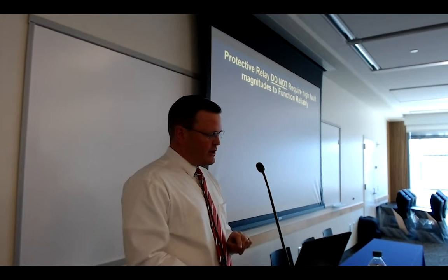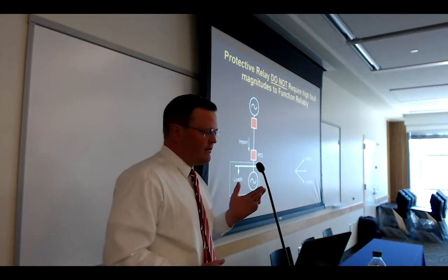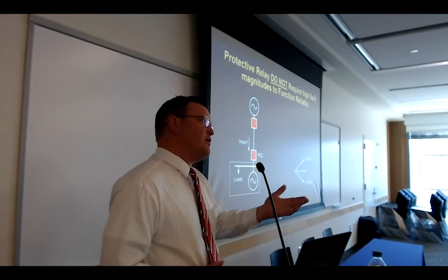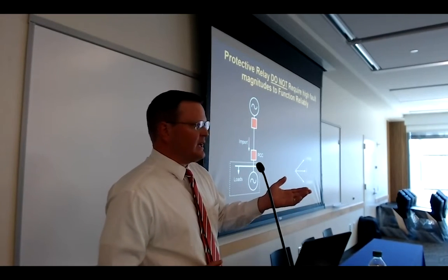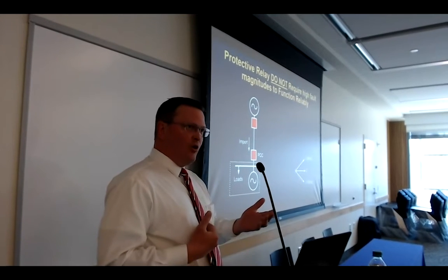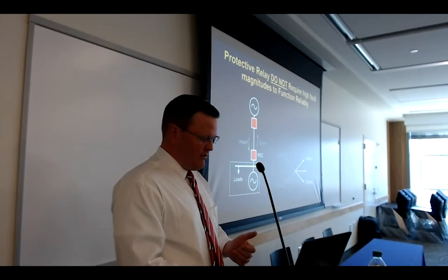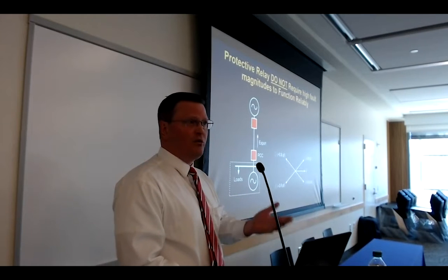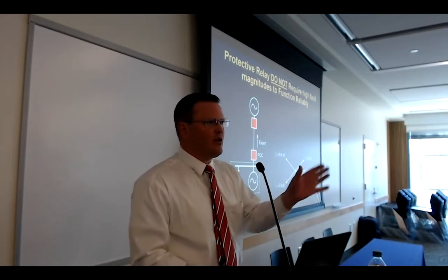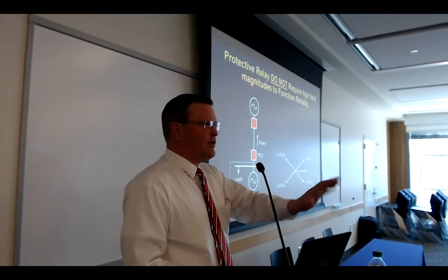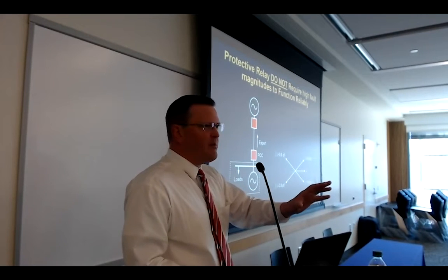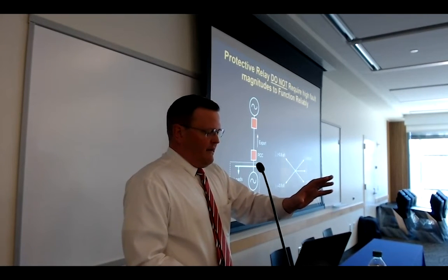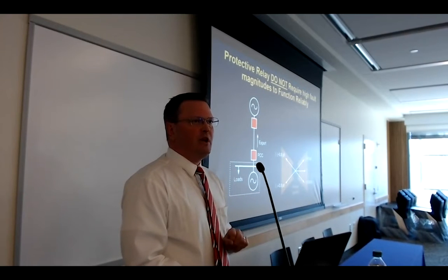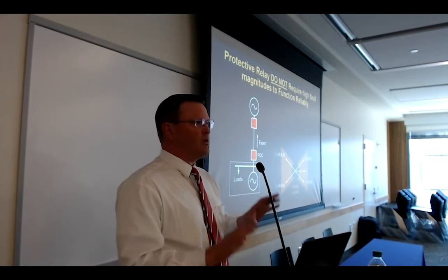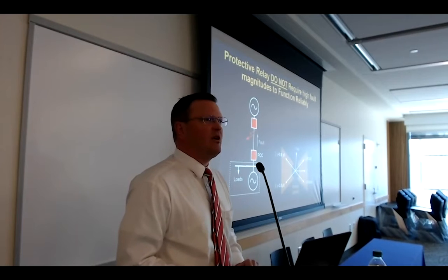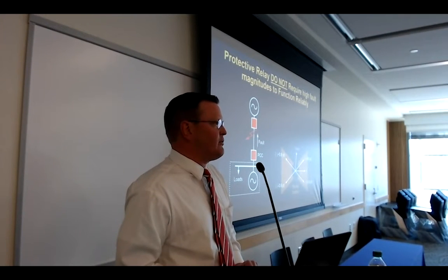Okay, so here's a scenario I'll explain. You have, again, that microgrid connected with some sort of generation connected to the macrogrid. During normal load import and export, you have phasor diagrams that look like this, currents related to voltage. I like this sort of diagram because anybody with nearly any engineering education can follow. But we know it's normal load behavior. We don't want to trip for normal load. We want to trip for abnormal current levels.